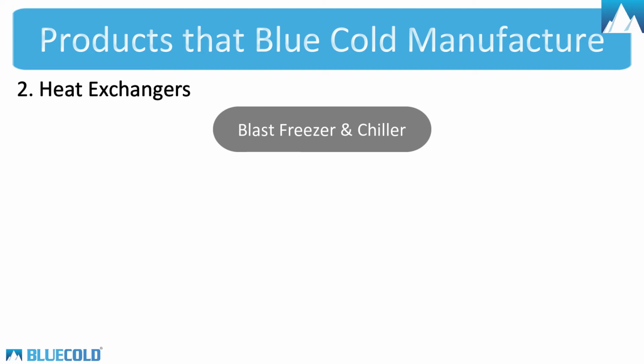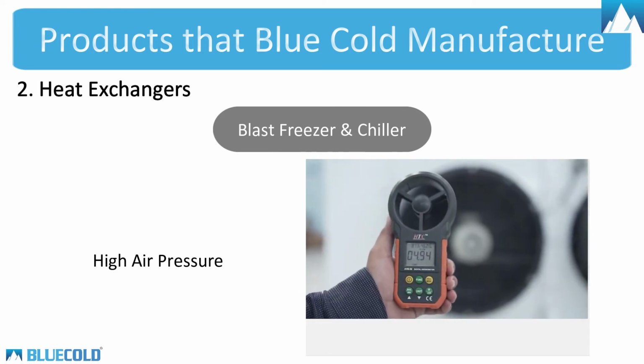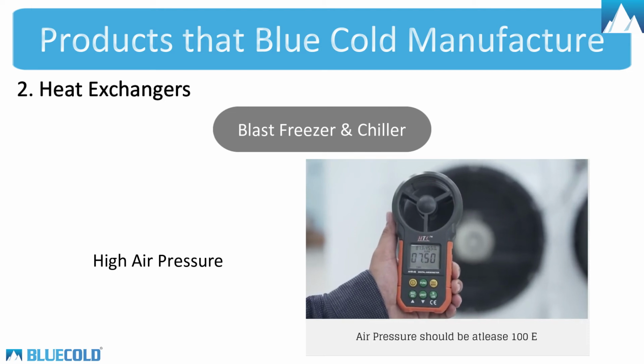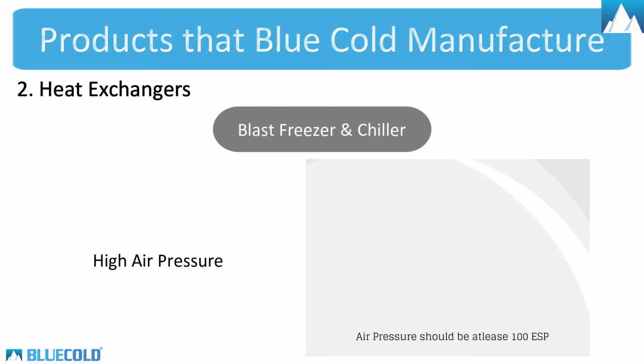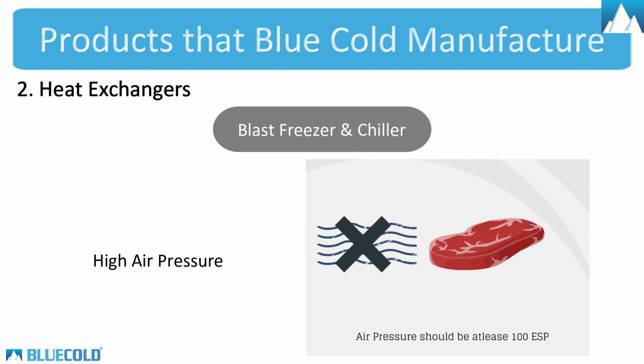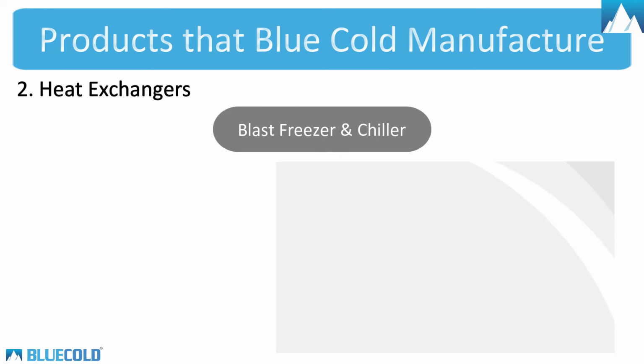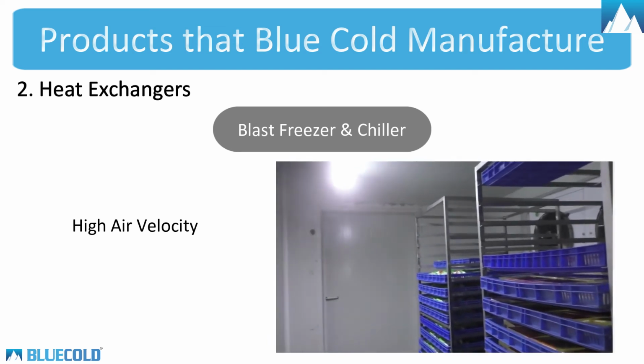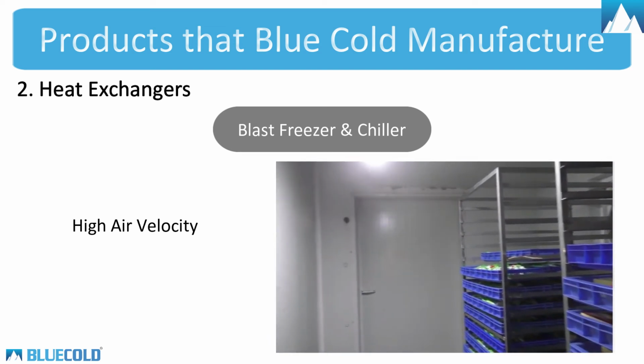Now let's look at important characteristics of our blast units. High air pressure. Our units can throw air at more than 100 ESP or external static pressure. If the air pressure is less than 100 ESP, then the cold air will not penetrate the product and the core or inside part of the product will not freeze completely and the quality of the food will deteriorate quickly. High air velocity. The higher the air velocity, the better the heat exchange between the cold air and food product. We maintain air velocity of about 5 meters per second to 6 meters per second to ensure that the heat exchange from the cold air to the food product is turbulent and fast.